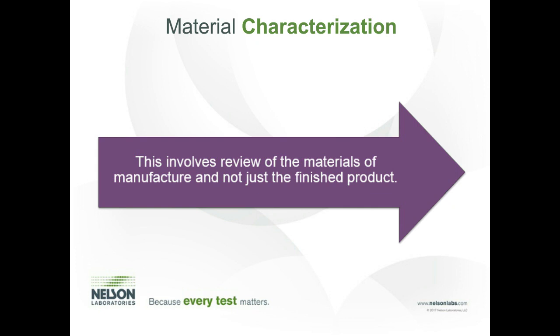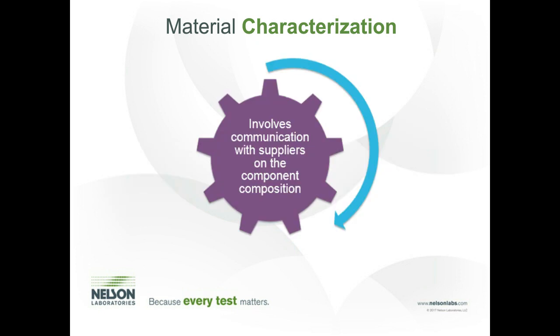But when you're doing a material characterization, sometimes and often we want to look at the impact of the material directly. The reason I recommend this is because in the future, if you end up using that material for another device, or if you end up changing that material, then we have an evaluation on that material directly, and not as it is through processing that you may not replicate. So it does depend on your individual company's needs, but remember that material characterization can be done on just the material and not on the final finished product, but your ultimate biocompatibility assessment needs to be on a final finished form.